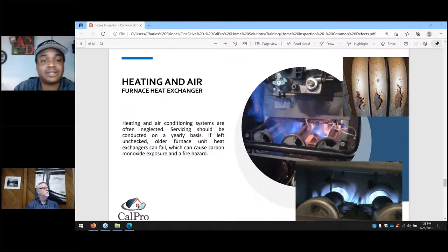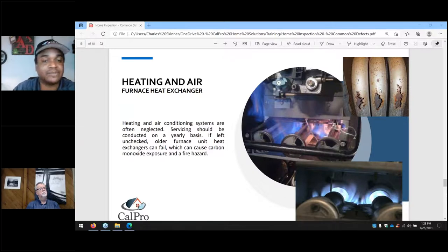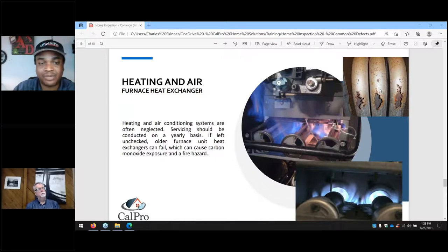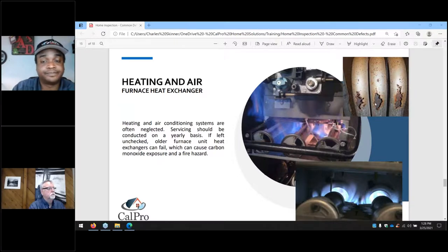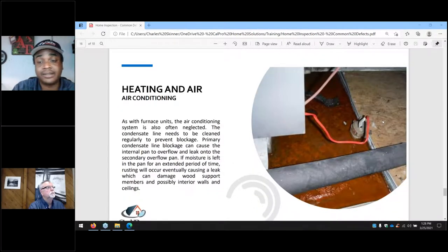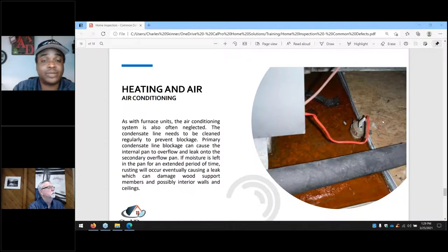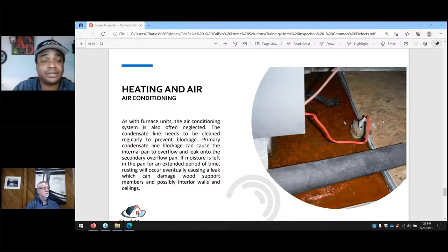If it's a newer system, it's usually not too big of a deal for our standard inspection. But if it's a 20 to 30 year old unit and they're not looking to replace it, even though it's operational, it would probably be best to have an HVAC company come by and do a more advanced inspection on those types of units. Without regular maintenance, you have condensate dripping into the attic pans, and a lot of damage can be caused by these.